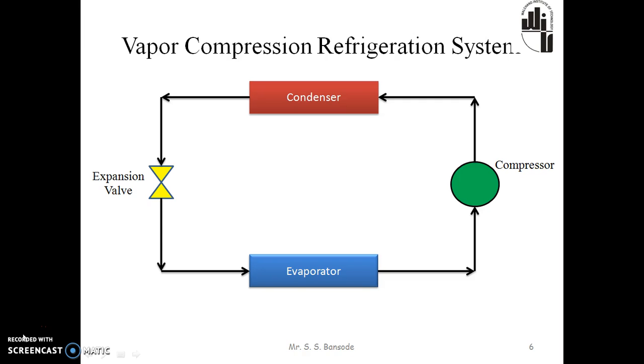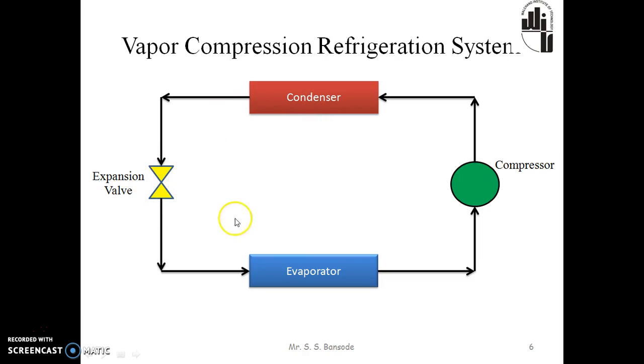During condensation, the refrigerant rejects heat to an external system like cooling water or to the atmosphere, and the refrigerant converts from vapor to liquid. As you can see in the schematic diagram of a vapor compression refrigeration system, the system mainly consists of a refrigerant compressor, a condenser, a refrigerant control valve called the expansion valve, and an evaporator.